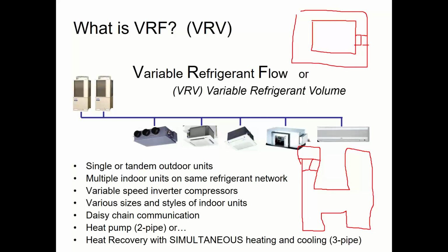The other thing that I can do is have a separate system. So I can have this VRF system with all these zones doing cooling. Then I could have, on my roof next to these guys, what's called a dedicated outdoor air system. Another acronym for you. And this is a whole other hour topic on its own, but a DOAS system, dedicated outdoor air system, brings 100% outside air in. A normal rooftop is bringing in 10, 20, 25%. This guy's bringing in 100% outside air, so he's designed to handle that. And he can still handle the dehumidification needs of that. He's specific to this. And then he is ducted in to each of the rooms.